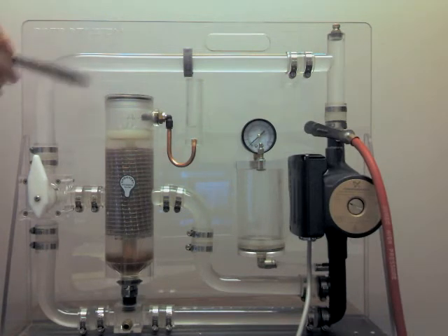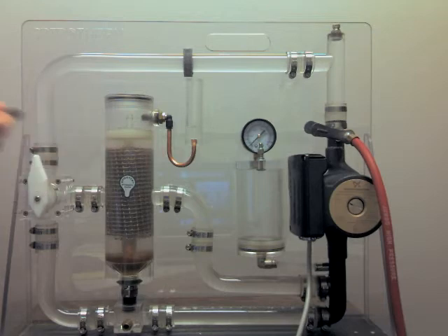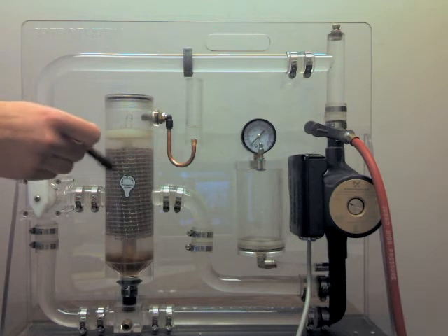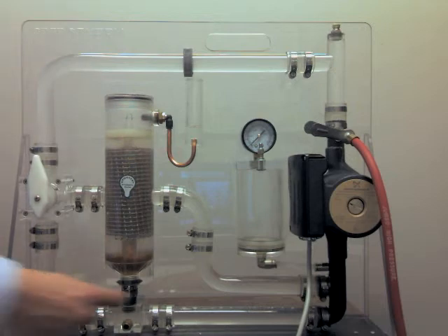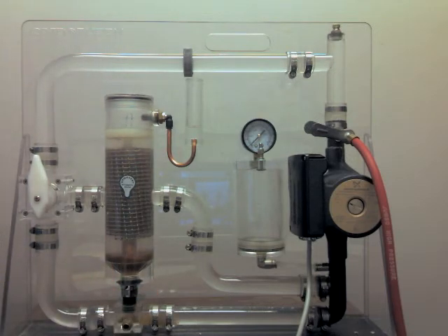And at the same time as it's removing bubbles, we actually have a small pressure drop by design in there to get as much of the dissolved air as Mother Nature will allow us to. That's breaking the air out of solution, so to speak, and it's either got something to cling to or eventually it hits the mesh and vents out at that point. And then what we're doing is we're stopping the corrosion from happening.